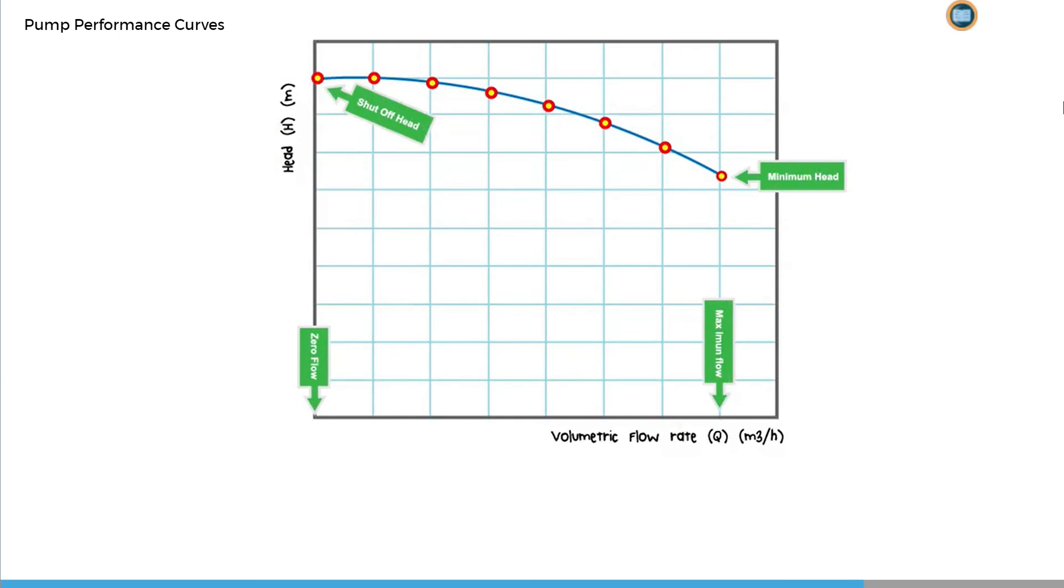While it is theoretically possible to operate the cargo pump under the full range of head conditions, you should avoid operating the centrifugal pump close to the shut-off point, because the flow rate is very restricted and the pump casing could overheat.